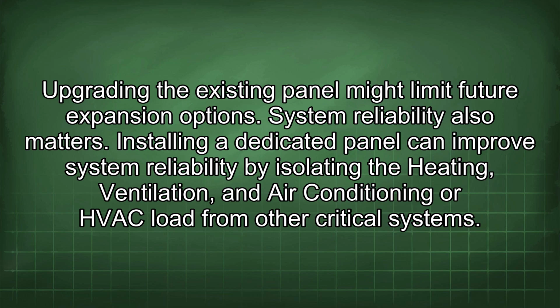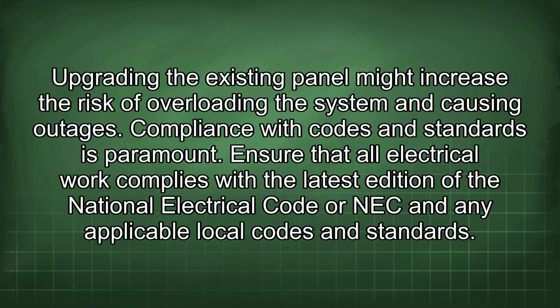System reliability also matters. Installing a dedicated panel can improve system reliability by isolating the heating, ventilation, and air conditioning or HVAC load from other critical systems. Upgrading the existing panel might increase the risk of overloading the system and causing outages.